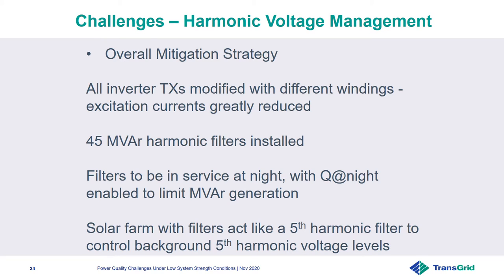So, how have we managed this challenge? Implementation of several things, including replacement of all 100 inverter transformers with an improved winding design to reduce excitation current, installation of 45 MVAr of harmonic filters, and we also identified the need for harmonic filters to remain in service at night, requiring night-time functionality to be enabled. With all this, the solar farm effectively acts as a fifth harmonic filter and controls background fifth harmonic voltage levels.